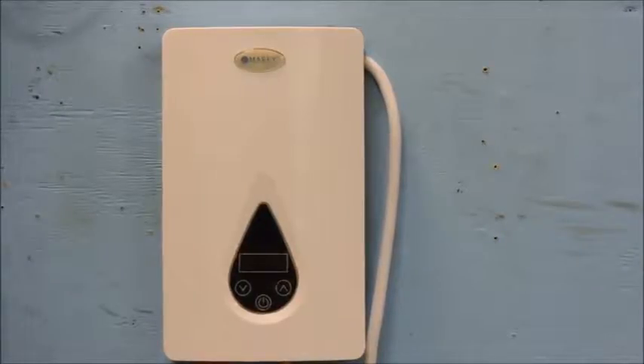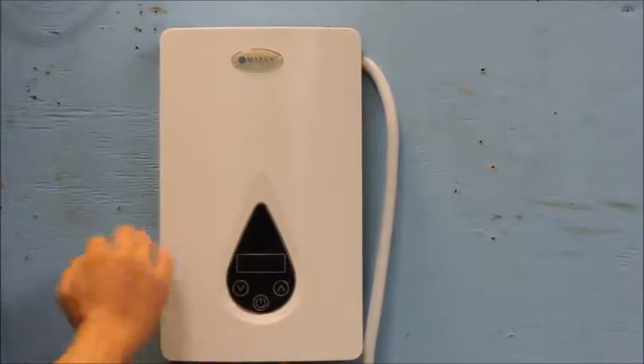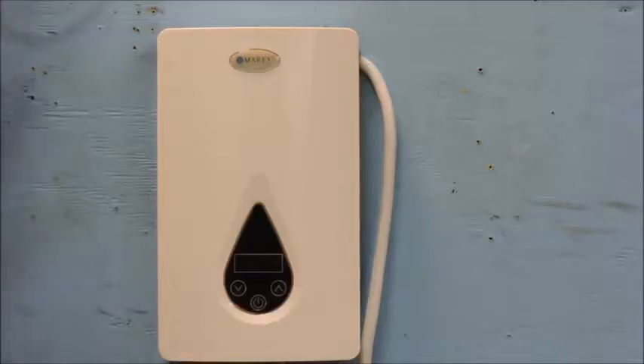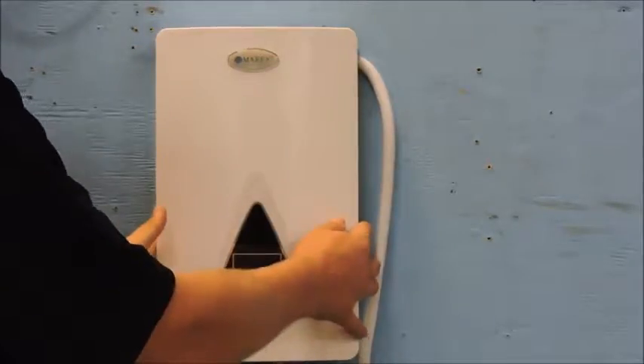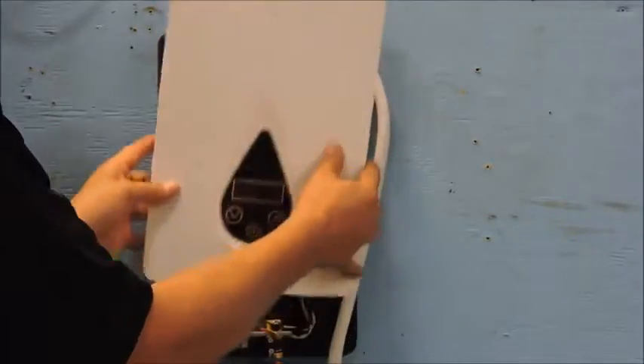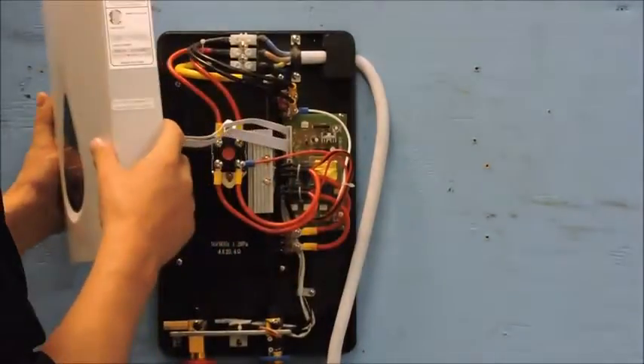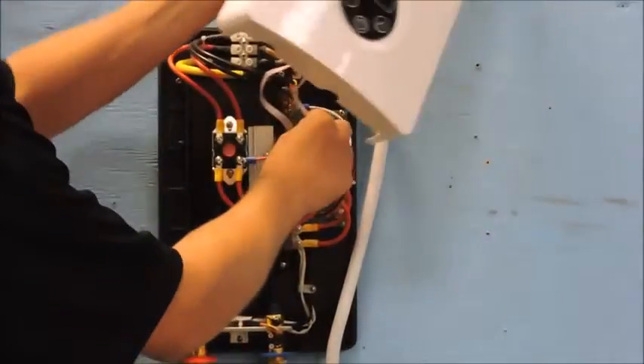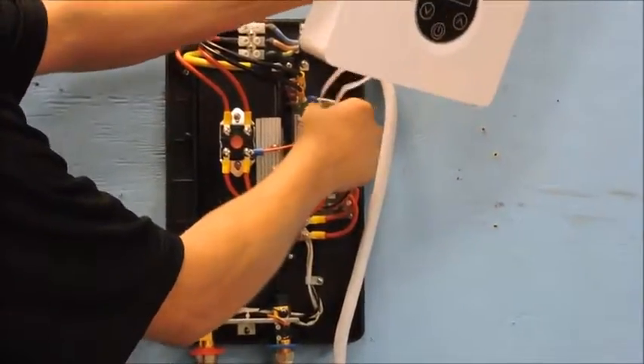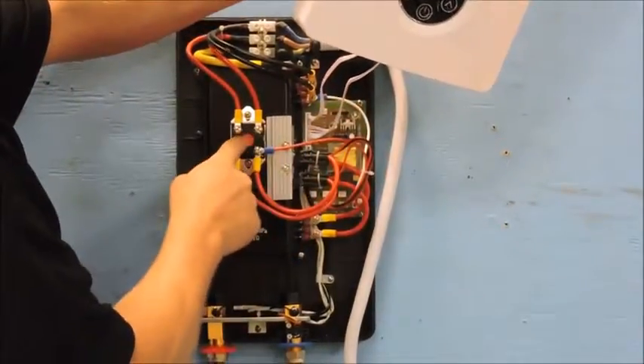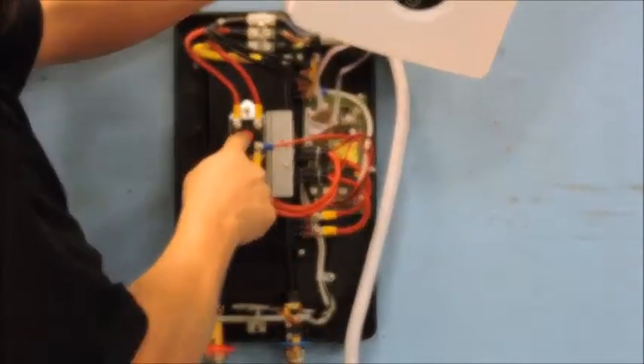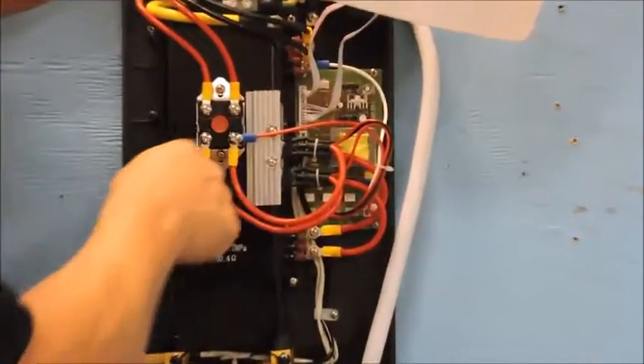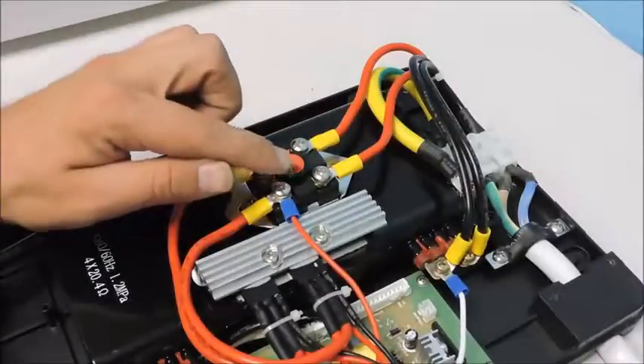The next problem we will go over is no display when power is supplied to the unit. Make sure that the power wires are correct as seen in the ECO110 installation video. If the wiring is correct, then shut off the power to the unit, confirm that the ribbon cable for the display board is secure in its location at the power board, and if all looks okay, then check to make sure that the red button on the overheat sensor has not popped up.